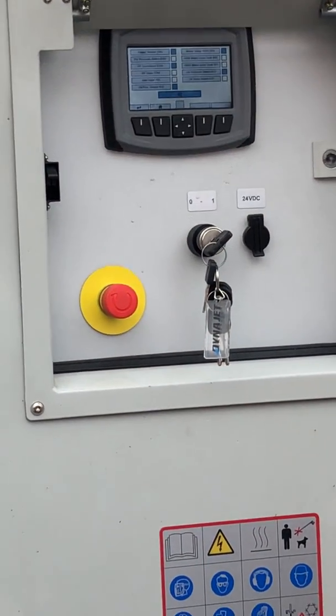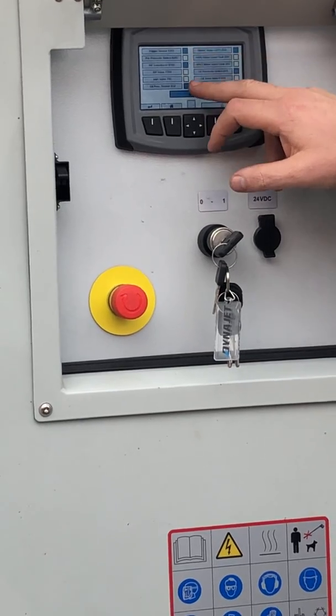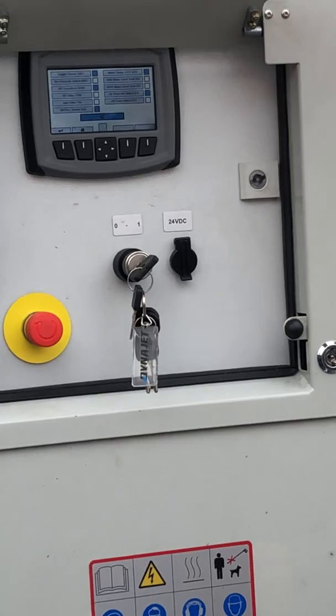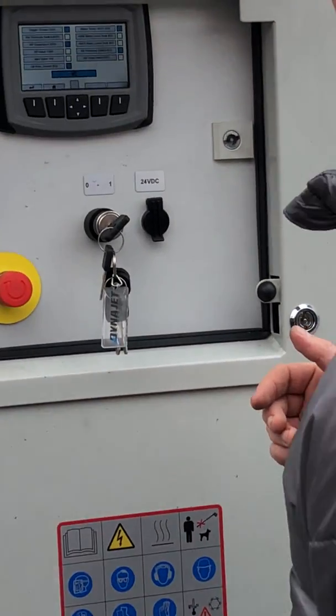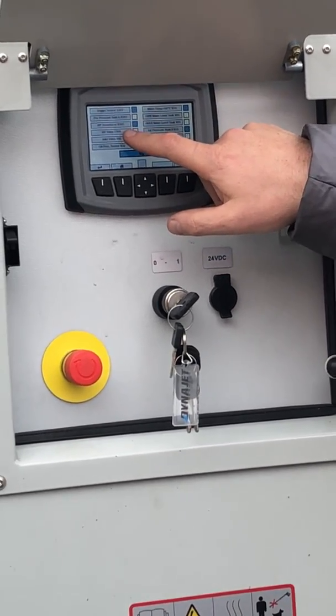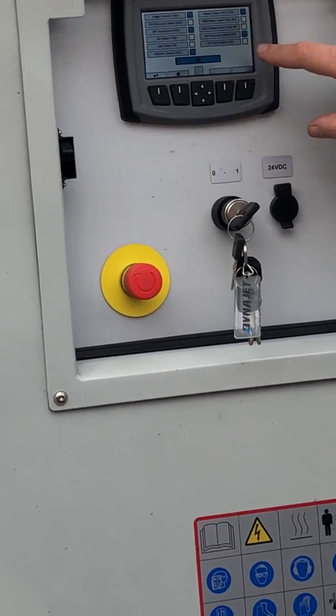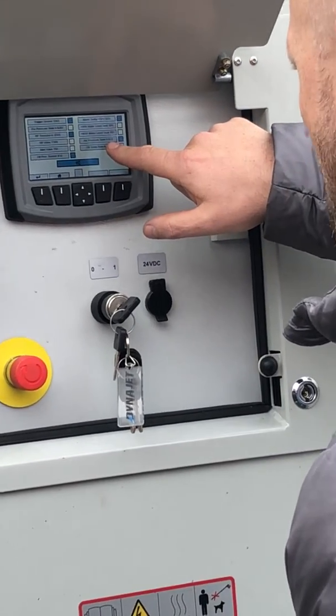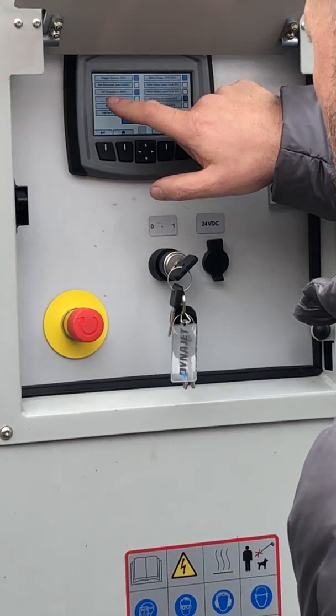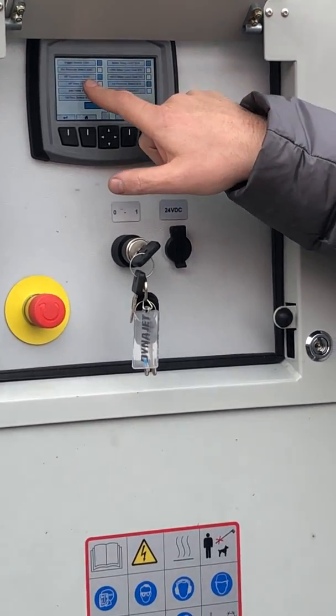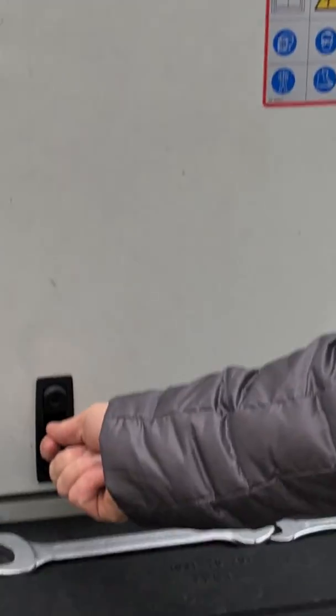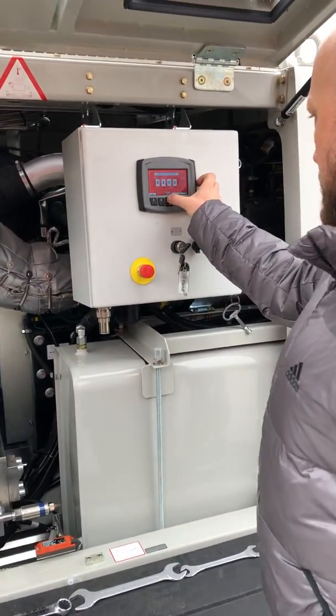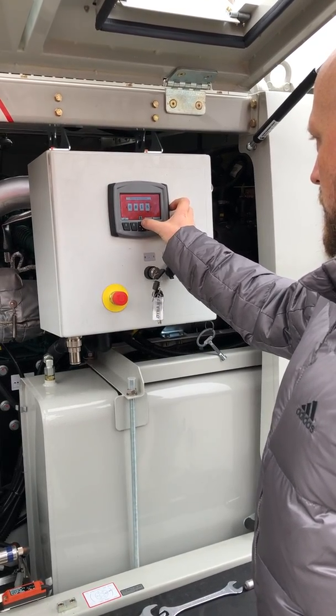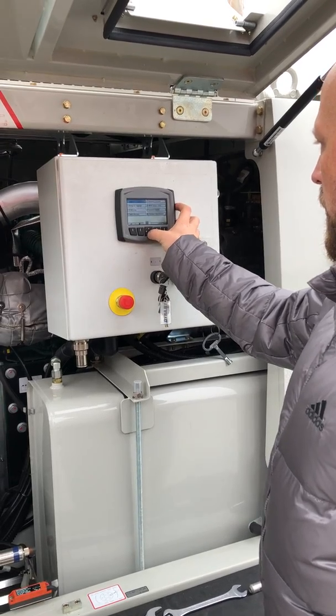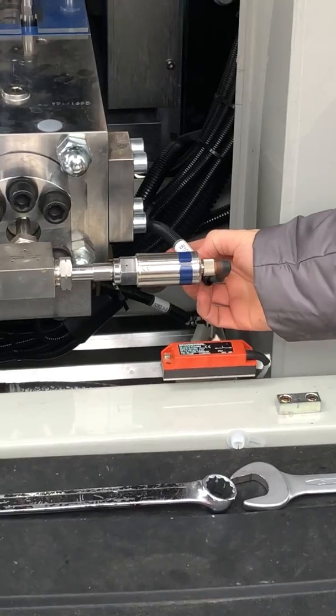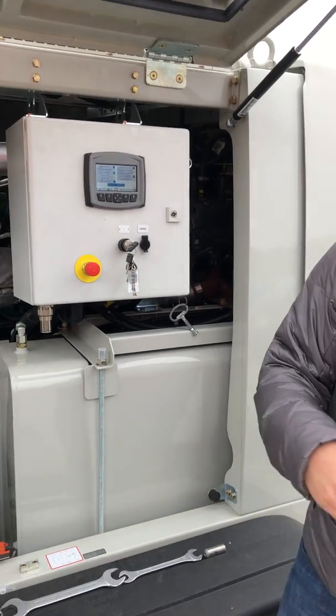We go to pump IOs. We see the trigger signal. We see a lot of signals. Are they on or off? This is very good for troubleshooting. Let's take the high pressure sensor. The high pressure transducer is B105. It shows B105 here, and it says B105 here, and it says B105 on the electric schematic. This is very good for troubleshooting.